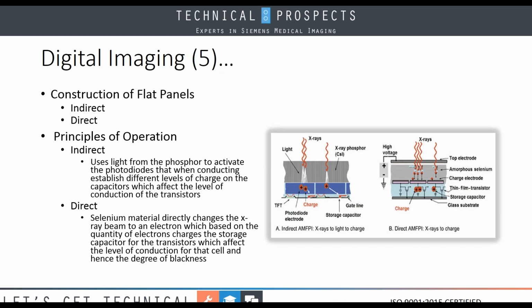When we look at the principles of operation, again, you see both illustrated in the picture, with the indirect on the left and the direct on the right. If you look at the indirect, here we're taking the light from the phosphor to activate the photodiodes that, when conducting, establish different levels of charge on the capacitors, which will affect the level of conduction of the transistors. This charge is what helps us determine the different shades of gray being sensed by our detectors. In the direct type of flat panel, we use selenium material, which will directly change the X-ray beam to an electron, which will then, based on the quantity of electrons, charge the storage capacitor for the transistors, which will affect the level of conduction for that cell and hence the degree of blackness. Two different ways of accomplishing the same thing, but you need to ensure you have the correct detector for your system.